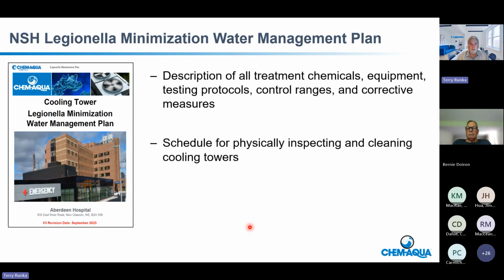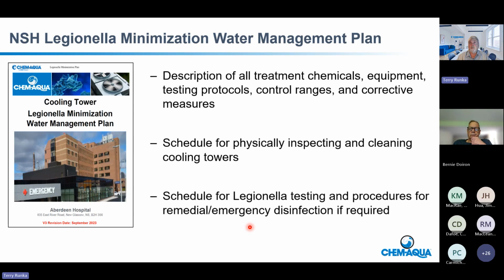Now, every single hospital in Nova Scotia Health has a water management treatment plan. It describes all the chemicals you use in your treatment. It describes the type of equipment you have, the risks, what tests you're supposed to do. More importantly, what control ranges are those tests supposed to be in? And if they're not in those control ranges, what can you do about it? They have a schedule for physically inspecting and cleaning your cooling towers, which is really, really important. And they have a schedule for Legionella testing.